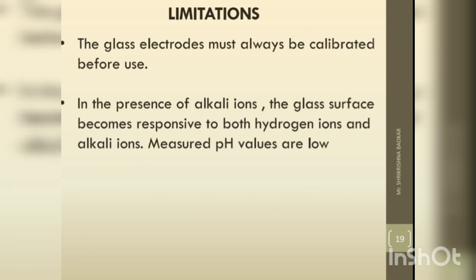Limitations: The glass electrode must always be calibrated before use. In the presence of alkali ions, the glass surface becomes responsive to both hydrogen ions and alkali ions, and the measured pH values are lower than actual.